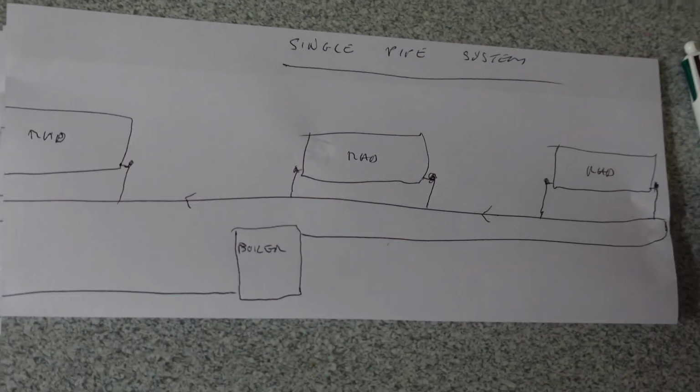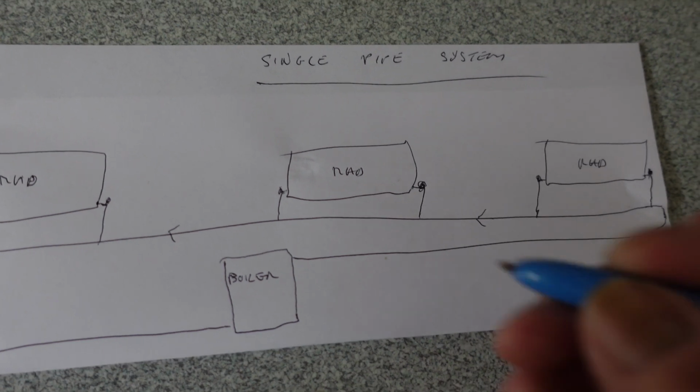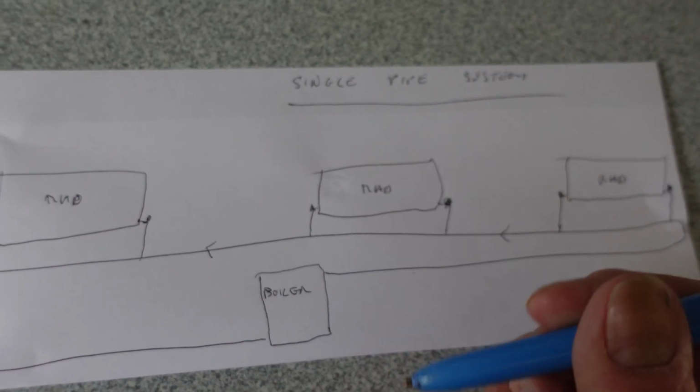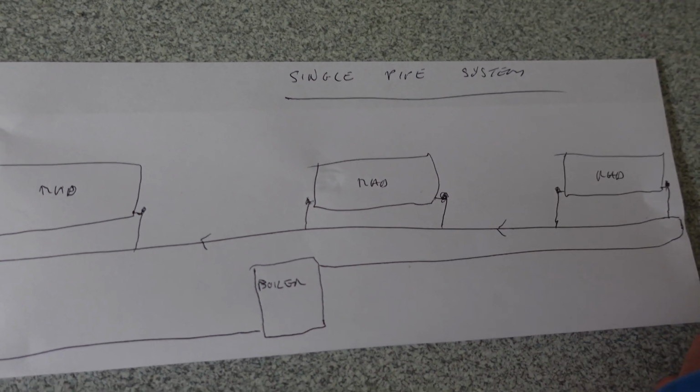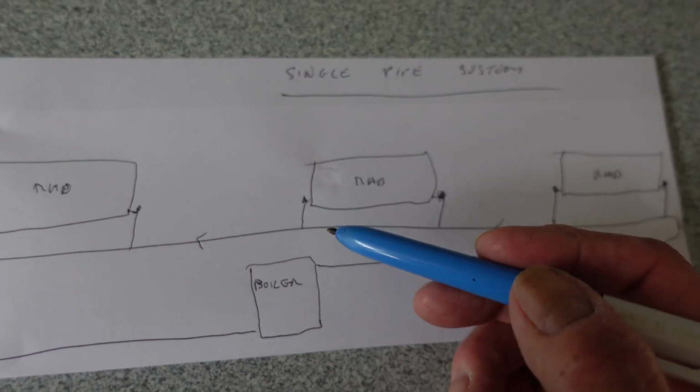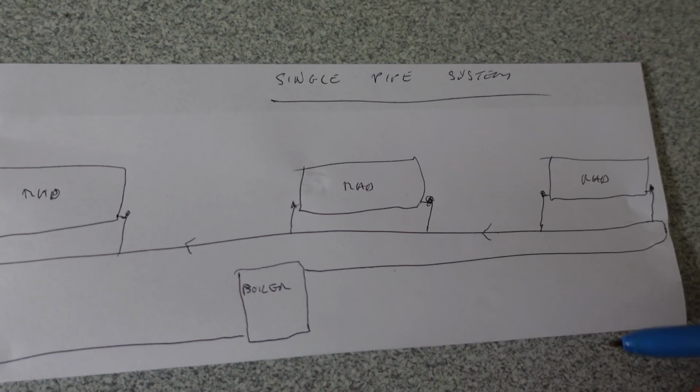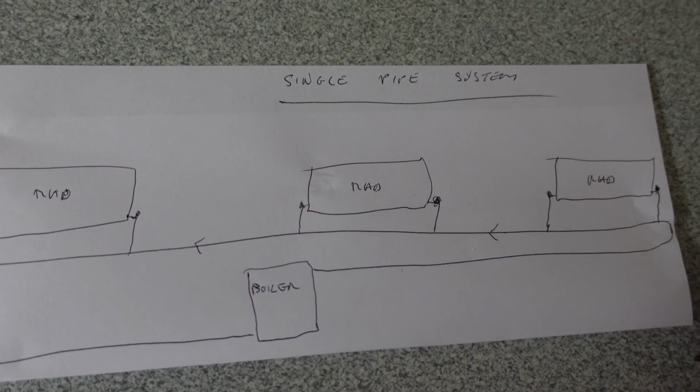Obviously if you've got a thermostatic rad valve on there, just turn that one. It doesn't matter these days whether that thermostatic rad valve is on the flow or the return. It did a few years back, because they never worked if they were fitted on the returns. If you had one there, it would never work, it would bang and clatter and do all sorts.